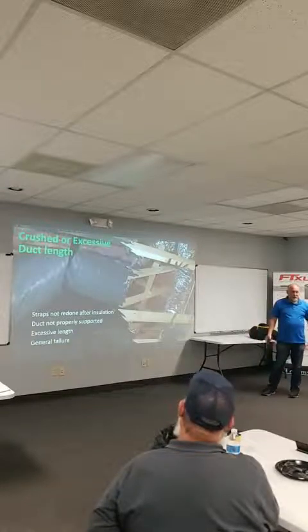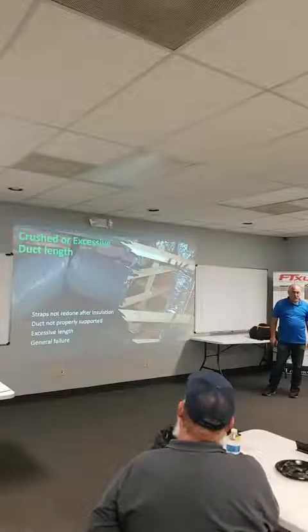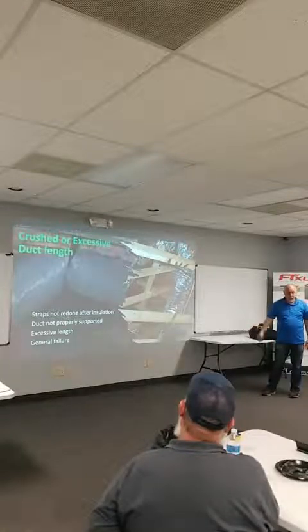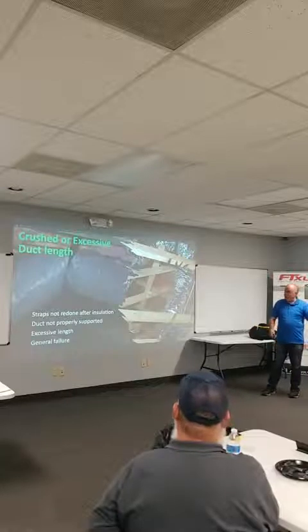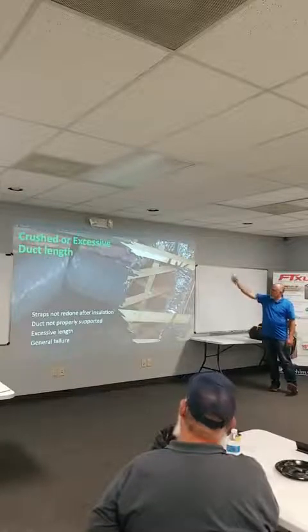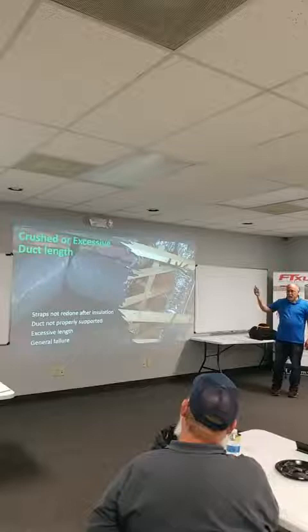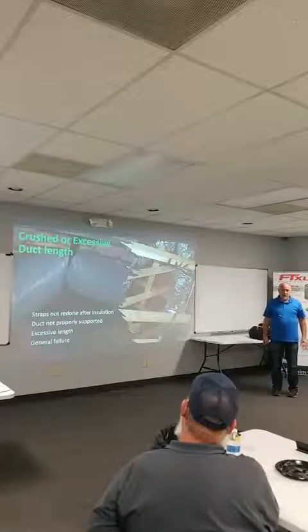Now they had 9 service techs out on this thing, and nobody went down and looked in the crawl space to see what the ductwork looked like. Nobody walked over and felt the air coming out of the register. They tried to solve everything at the equipment, right? And then this was excessive flex duct length.